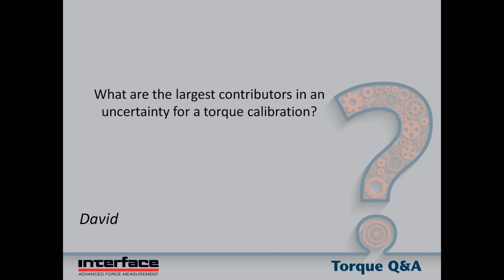Well, pretty much I think you hit on the majority of them, Keith. As I, in the field, whether it be at our factory or in the field, by far and away the most common method for calibrating a torque sensor is through the application of a moment arm and dead weights. And the dead weights are typically certified by a governing body and are traceable.